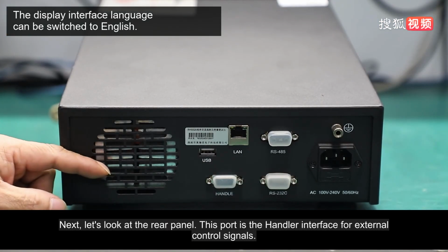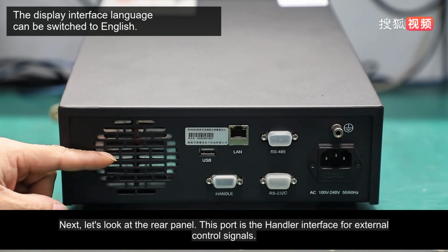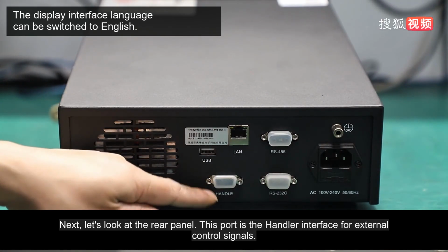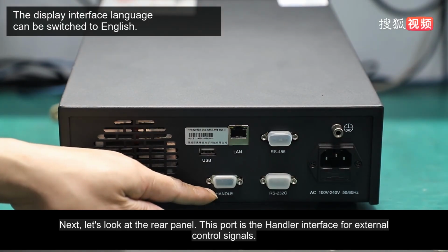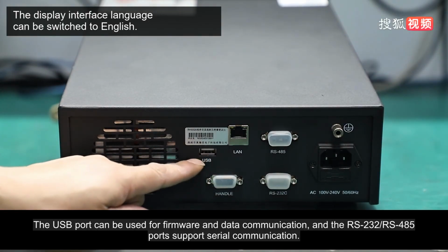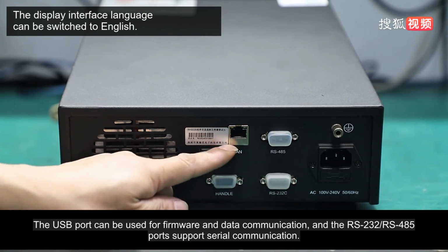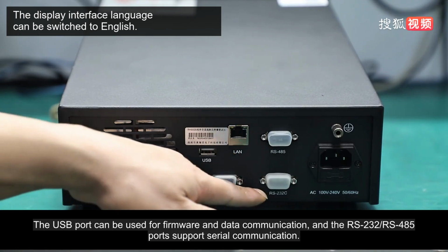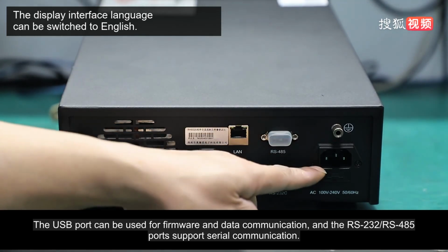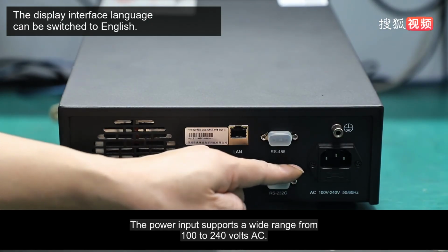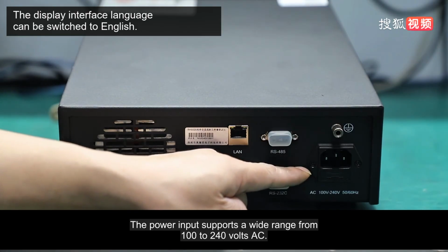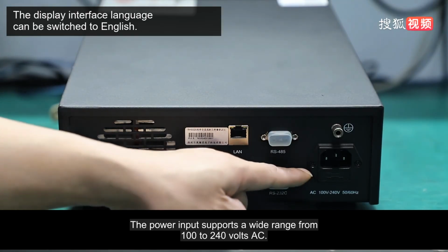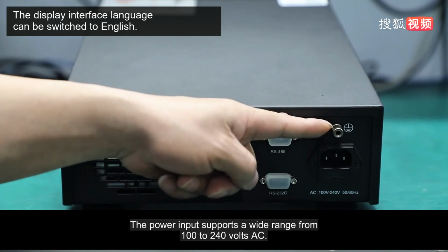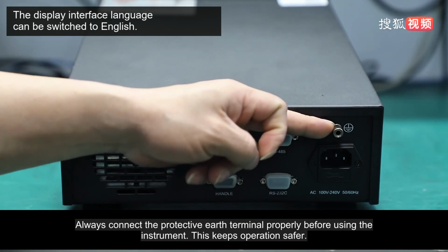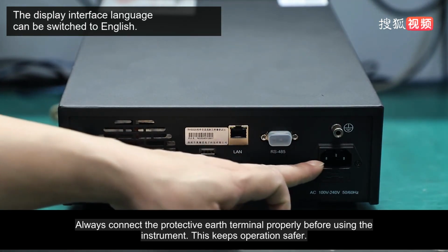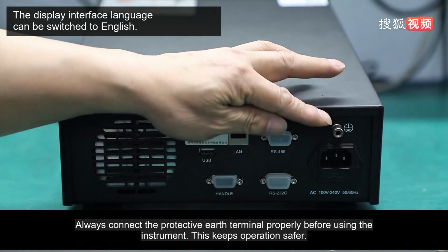Next, let's look at the rear panel. This port is the handler interface for external control signals. The USB port can be used for firmware and data communication, and the RS-232/RS-485 ports support serial communication. The power input supports a wide range from 100 to 240 volts AC. Always connect the protective earth terminal properly before using the instrument. This keeps operation safer.